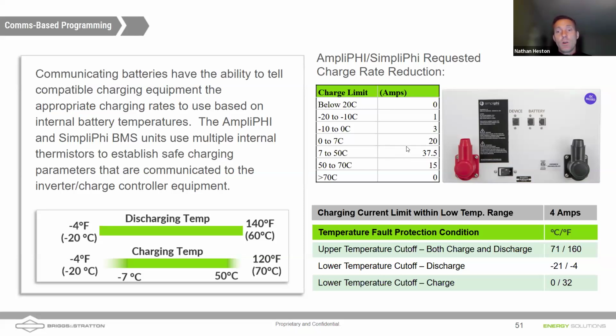So a less efficient low temperature battery can heat itself up, and so we can ramp the rate at which we heat that battery up during a discharge cycle, or even by charging slowly, allowing the battery cells themselves to get warmer and then increasing that charge rate. So we have an expanded charging temperature range for our batteries that normally exceeds the competition.